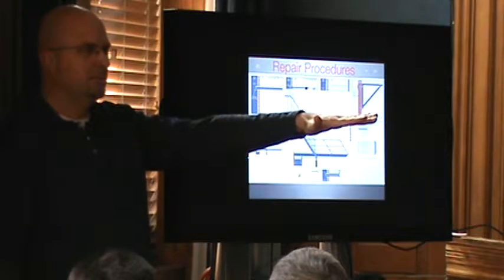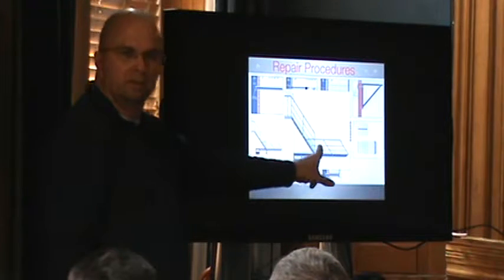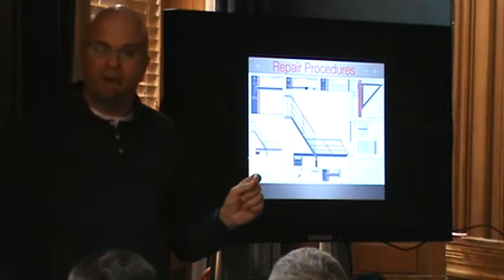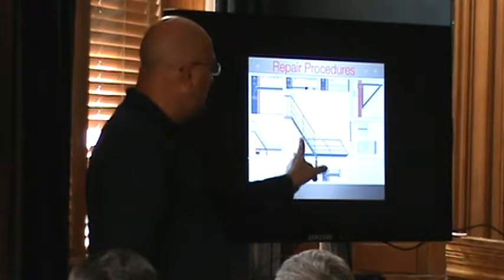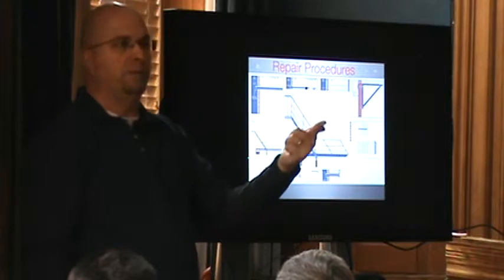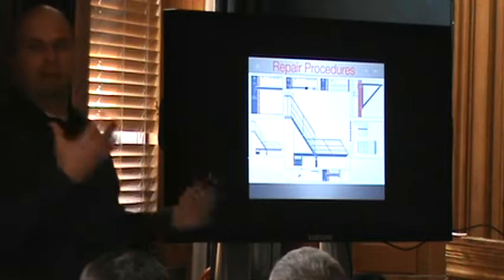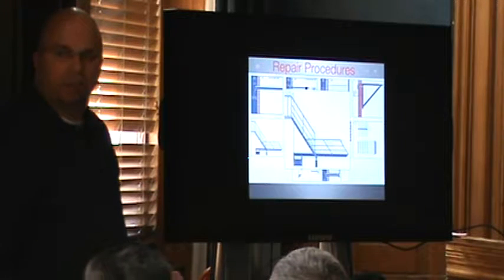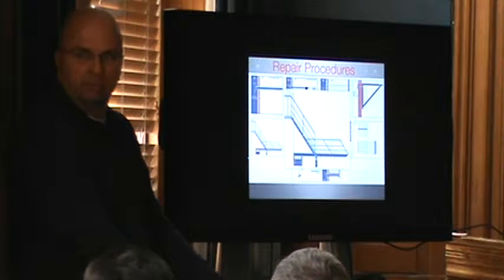Is it legal? No. So if you see any chains on cantilevers, that's somebody who's modified it and weighted it backwards. So now let's talk about what these release arms are supposed to be for. Single action requiring no special knowledge. I've got a woman who is egressing a fire. She's got a child with her. Do you drag the child or do you put the child in front of you? In front.